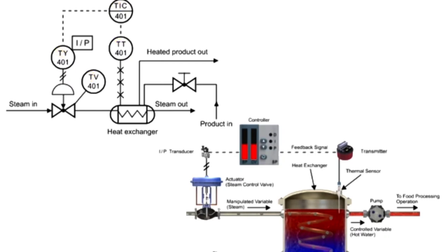The instrument connected to the heat exchanger contains two other types of information. The second letter in the functional identifier indicates it is a transmitter. And the balloon with no line inside its symbol indicates the device is field mounted.